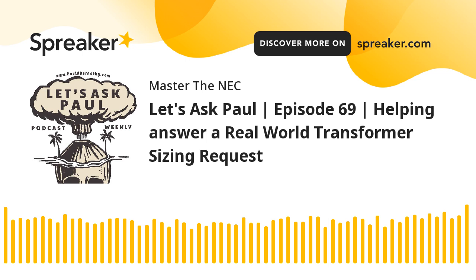And then number 4 says the disconnecting means for the conductors is installed in a readily accessible location complying with one of the following. Okay, so we're talking about that disconnecting means that is required for you to terminate those secondary conductors into, which in our case is going to serve double duty, right? It's also going to be the disconnect for the HVAC unit. That's okay. But it says outside of the building or structure. Okay, we don't really need to go any further because it is all outside. Well, B, it says inside nearest the point of entrance of the conductors. Well, we're not penetrating, so that one doesn't apply.